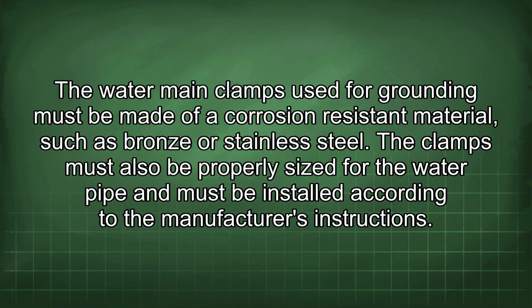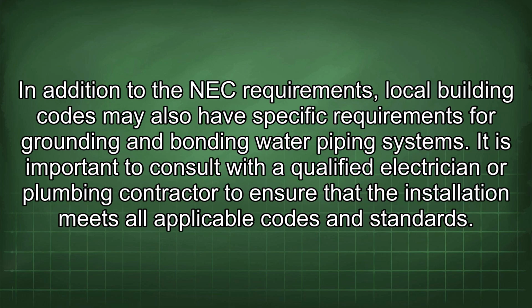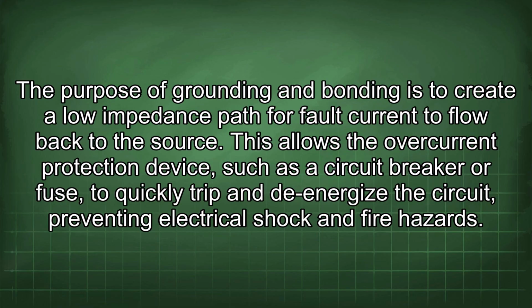The water main clamps used for grounding must be made of a corrosion-resistant material such as bronze or stainless steel. The clamps must also be properly sized for the water pipe and must be installed according to the manufacturer's instructions. In addition to the NEC requirements, local building codes may also have specific requirements for grounding and bonding water piping systems. It is important to consult with a qualified electrician or plumbing contractor to ensure that the installation meets all applicable codes and standards. The purpose of grounding and bonding is to create a low impedance path for fault current to flow back to the source.